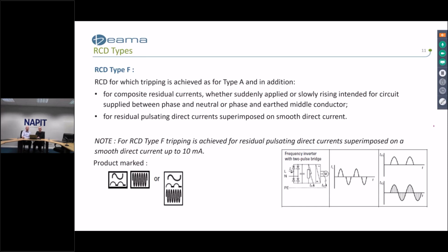And again, in terms of identification, the product will be marked, as shown on the slide, with the two types of waveform, either side by side or one above the other. Sorry, just to point out, the waveform on the bottom right-hand side of the slide is just an example of the type of fault currents that the Type F will respond to. So in the bottom right-hand corner, it looks as though it's shaded, but it's actually a high-frequency AC waveform created by the control system. A Type AC or Type A would not respond to this type of waveform, but a Type F will.